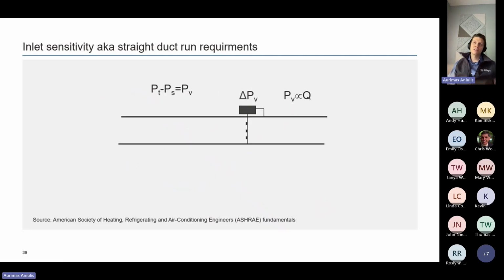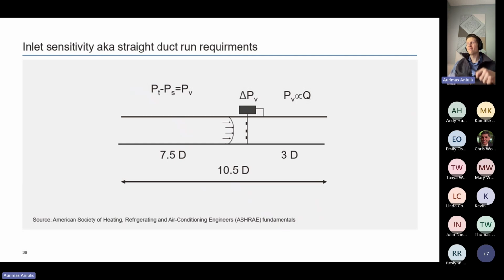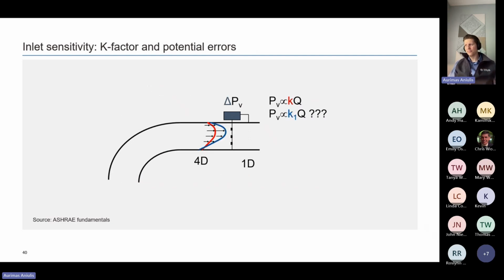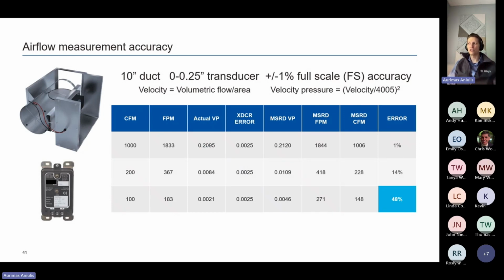Lastly, inlet sensitivity, also known as straight duct requirements. If you're using the delta P reading, most of us understand that air is like water, and it settles and it's turbulent. So you'll see that there are some straight duct requirements, which sometimes become prohibitive from a design standpoint. And that's where Venturi, again, has an advantage over sensor-based digital devices that require a fairly laminar flow to read an average pressure of the duct to get you a correct CFM reading. These slides are showing those variables in effect when you have duct bends. Those variables can be extrapolated to a margin of error, which of course can be managed and maintained, but it shows that there's a level of control and accuracy that needs to be managed when you're using devices that require straight duct airflows.